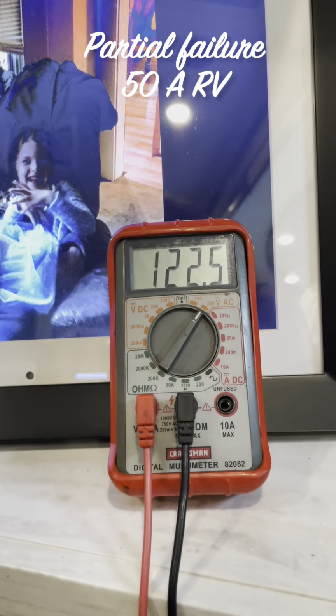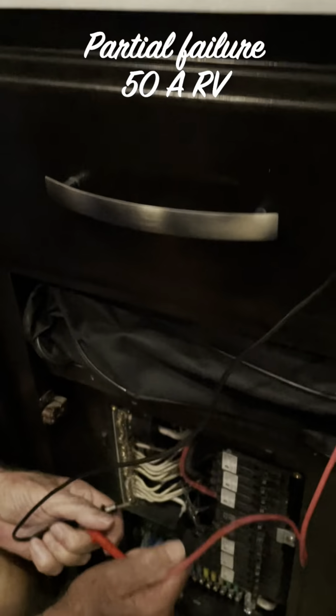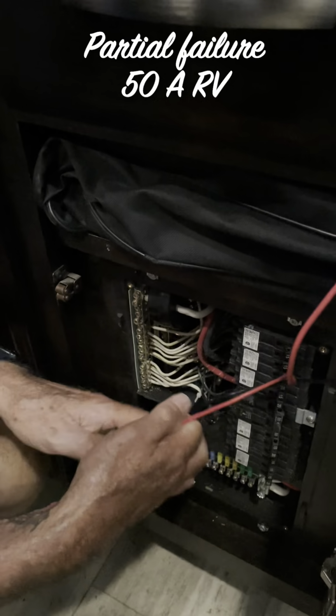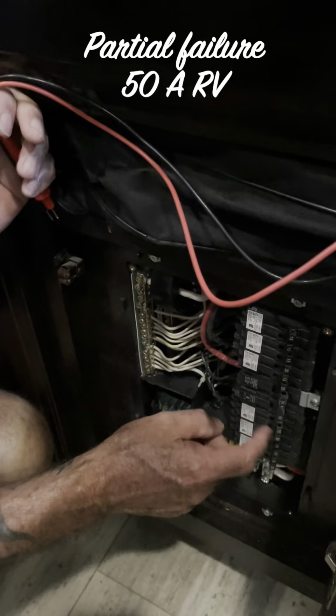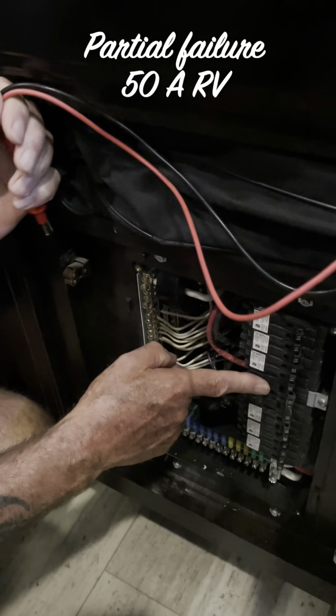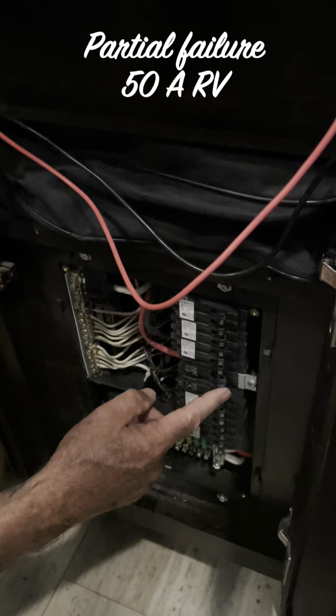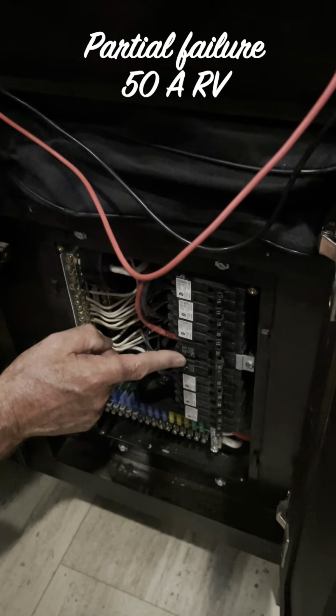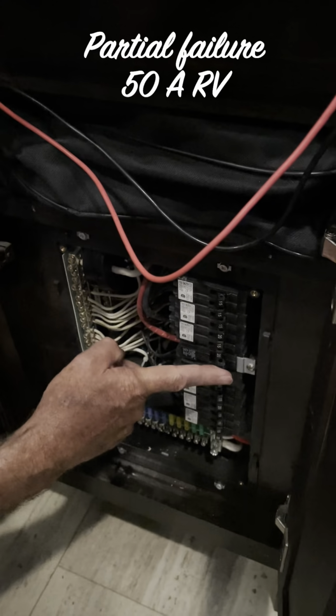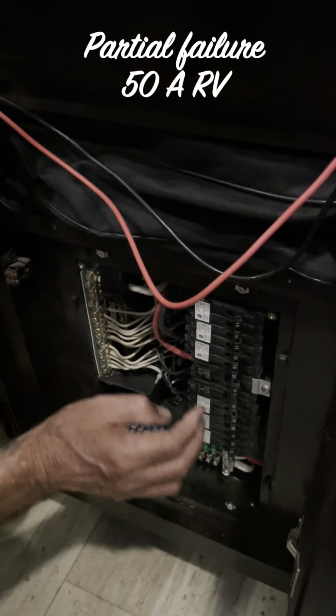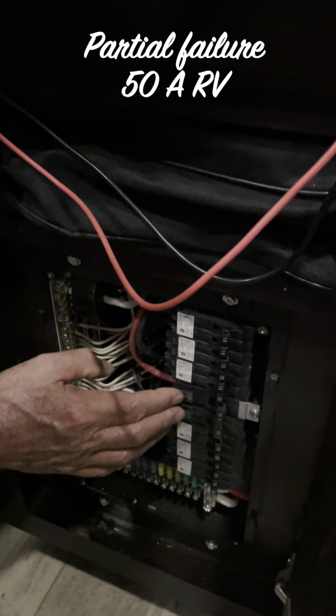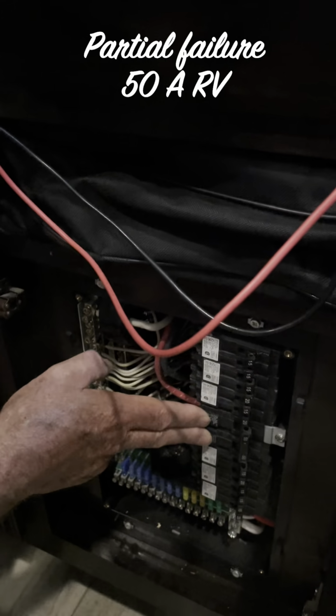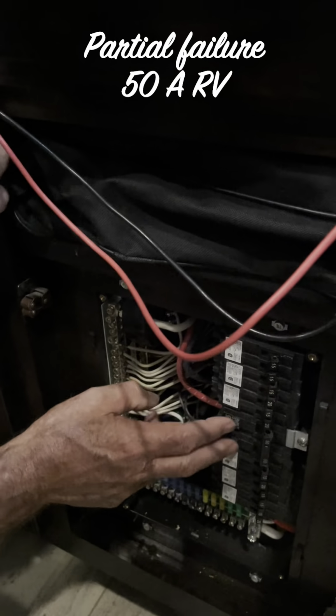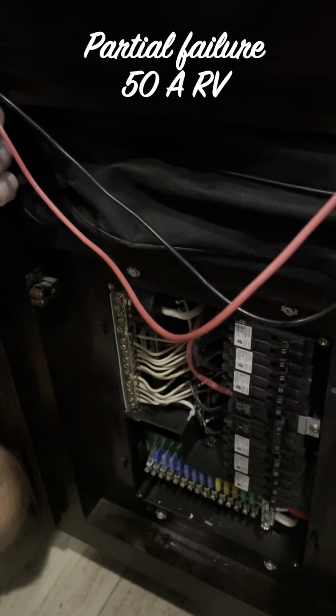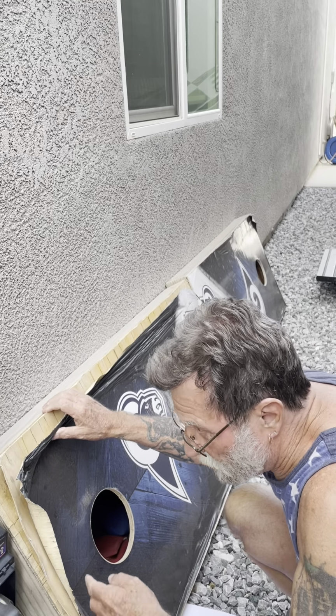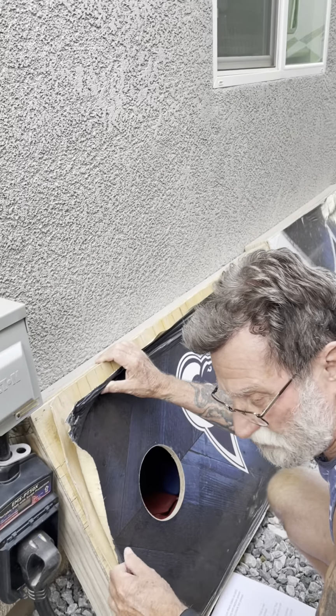If one of these does not read 120 volts, while it's unlikely, it is remotely possible that one breaker tripped without the other. So you would reset these by shutting the breaker off, waiting a second or two, turning the breaker back on, and testing it. If that still does not restore power, we want to find out where we're losing power before we actually start replacing circuit breakers. So you would go to your pedestal and look for a tripped circuit breaker.